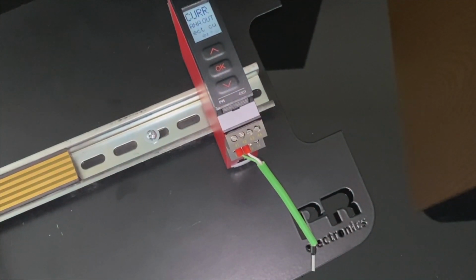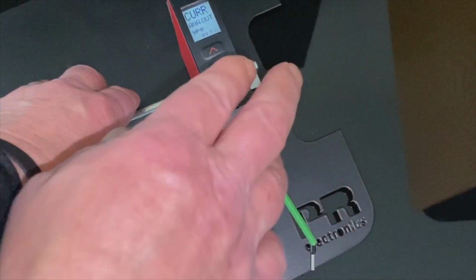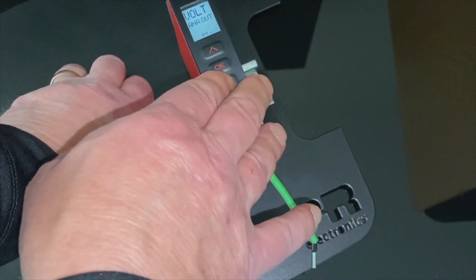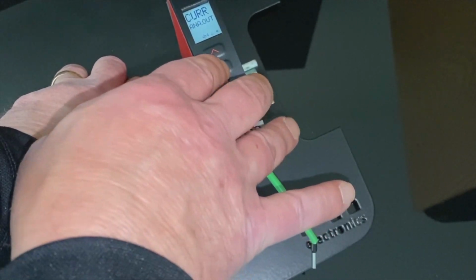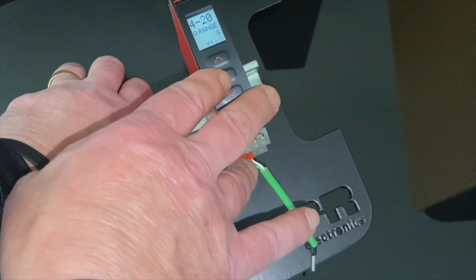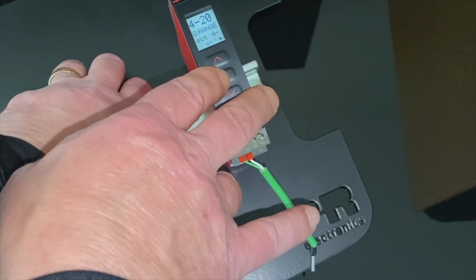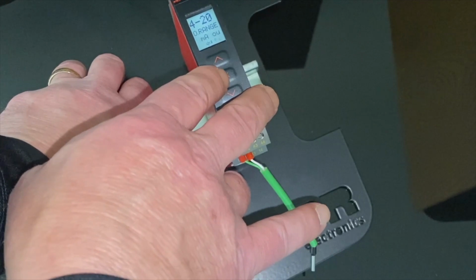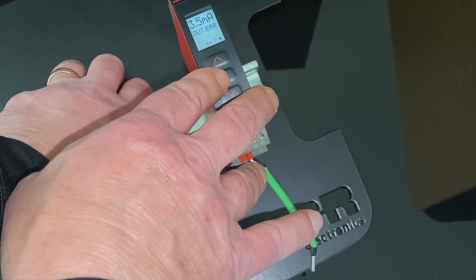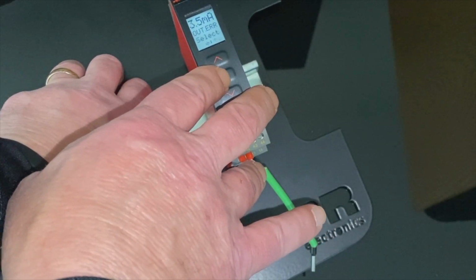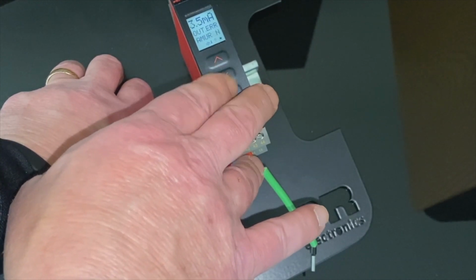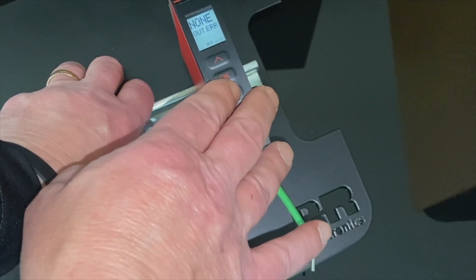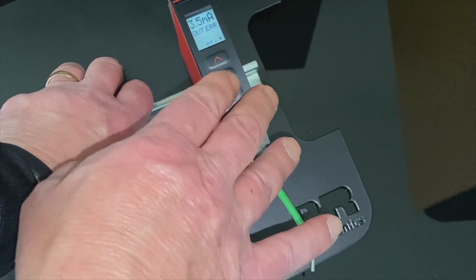Okay, you've told the 4116 what your inputs are, what your relays are going to do, and now you have an output that you have a choice with. You can select from either current or voltage. If you select current, you can see 4 to 20 will come up, but we have 0 to 20, 20 to 4, all of the variations of the current output. You can select either a high or a low default, 3.5 or 23, or none, 23 milliamp.